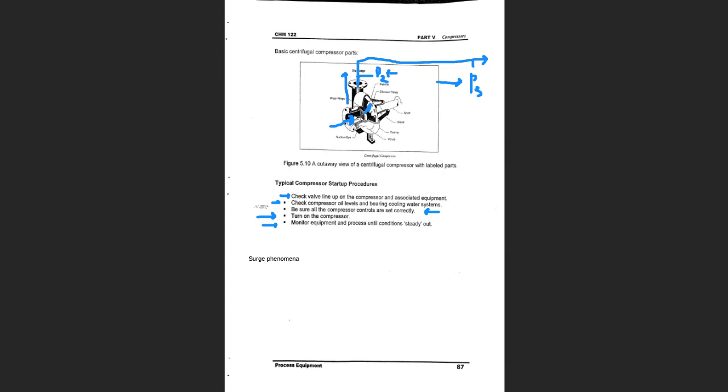فتبدأ الحرارة ترتفع بشكل كبير جدا في الكمبرسور، ما هو زي الليكويدز أو البامبس، وهذا الشيء راح يحدث ضرر كبير جدا. So one solution, guys, to fix this surge phenomena is that they have to reduce the pressure at P3, and one way to do that is by having a pipeline known as the kickback line. هذا الكيكباك يا شباب يسمح للجزء من الغاز اللي موجود في النقطة هذه P3 إنه يرجع مرة ثانية ويدخل من جديد على السكشن حق البامب.